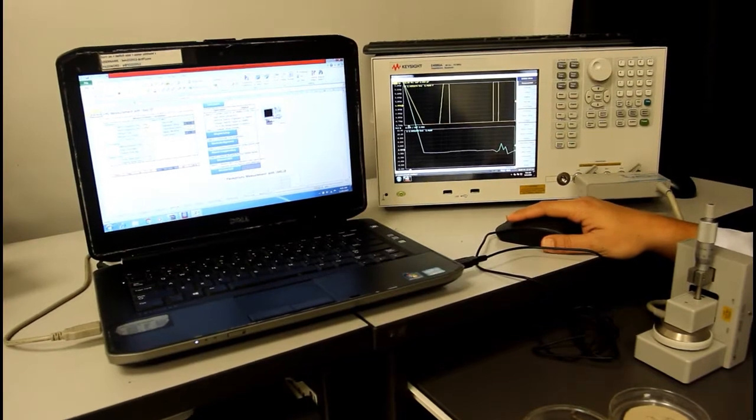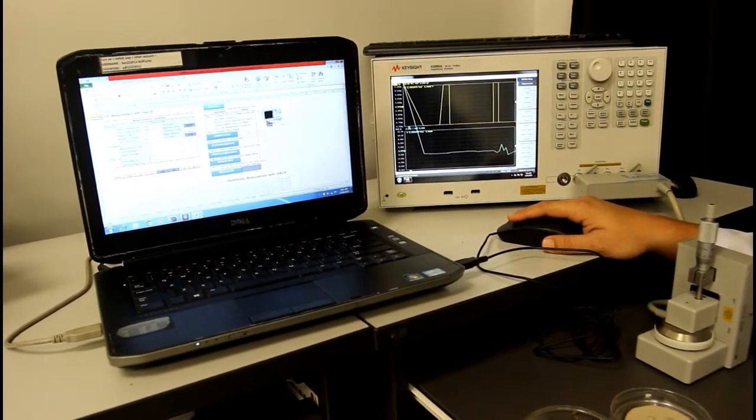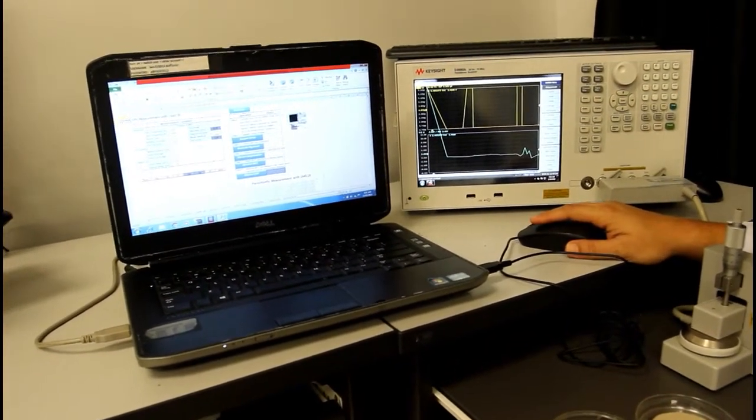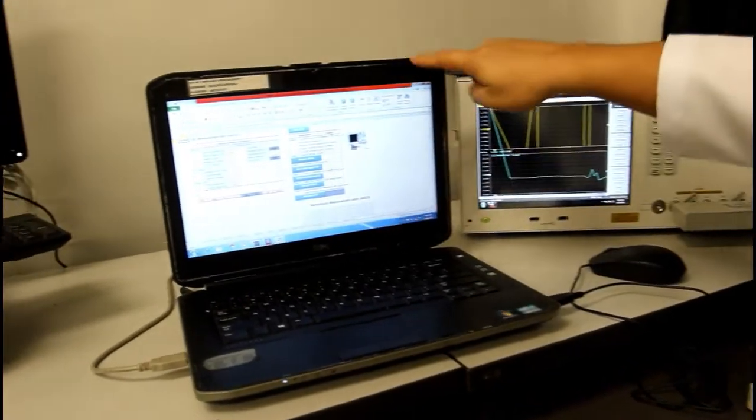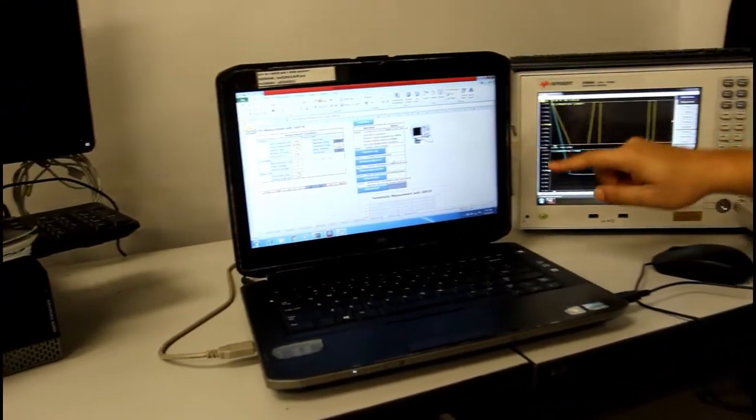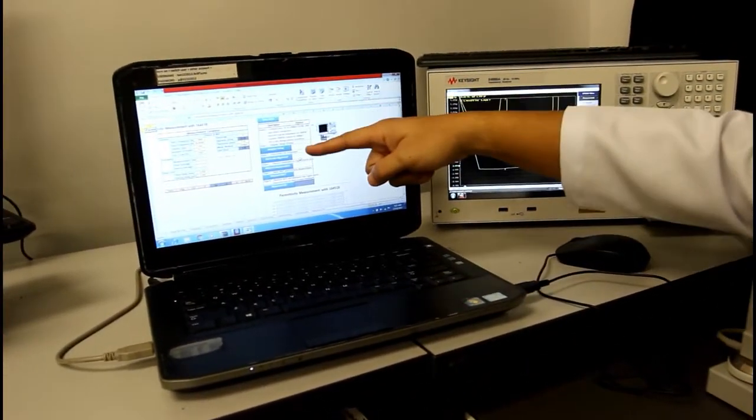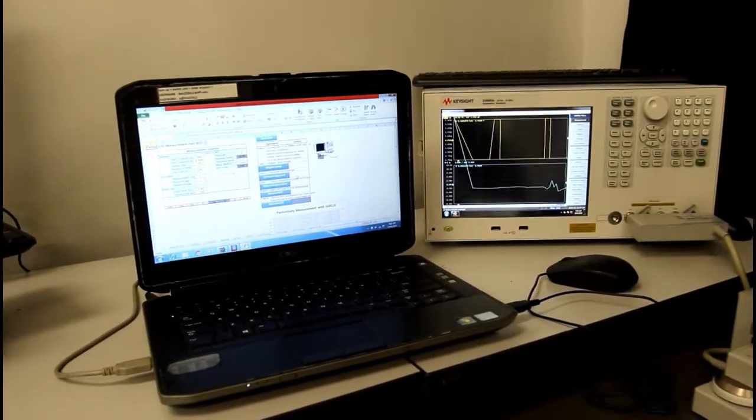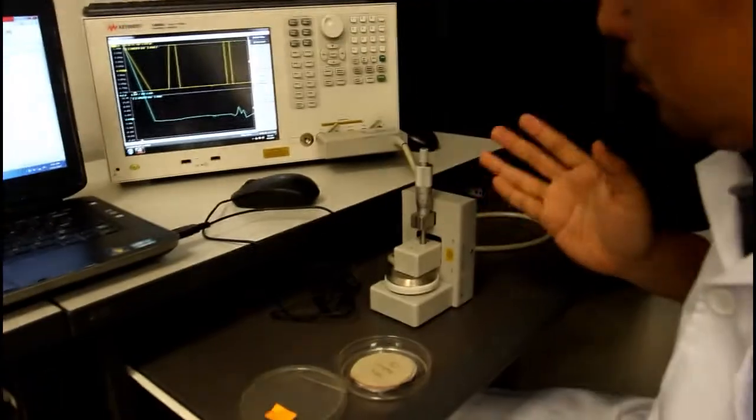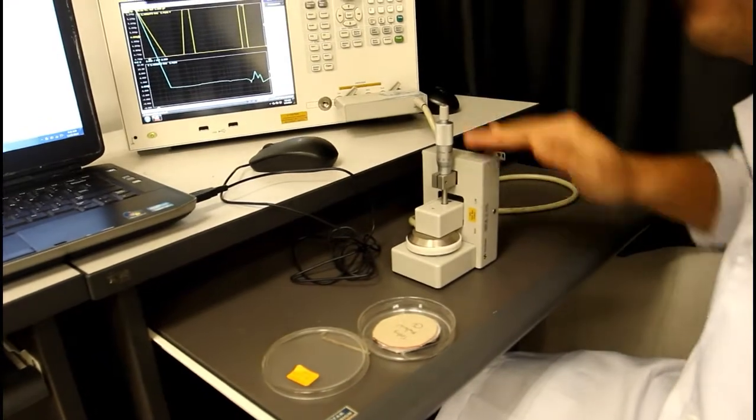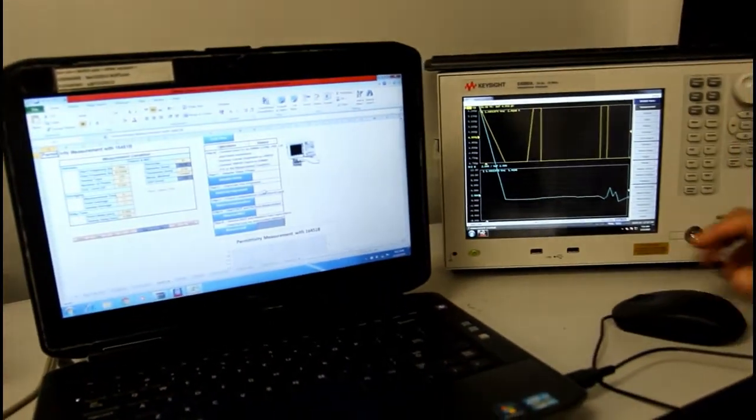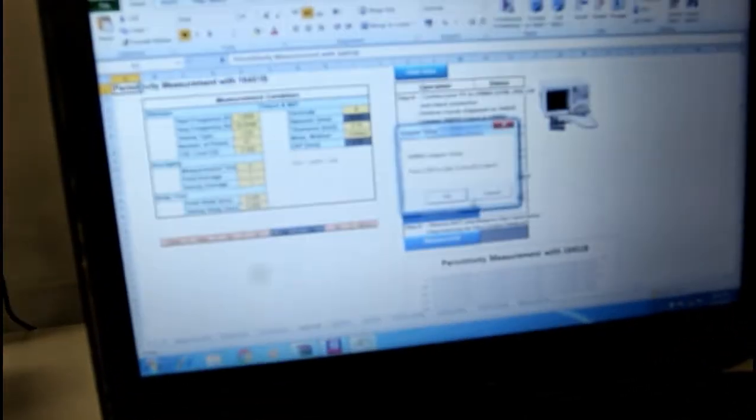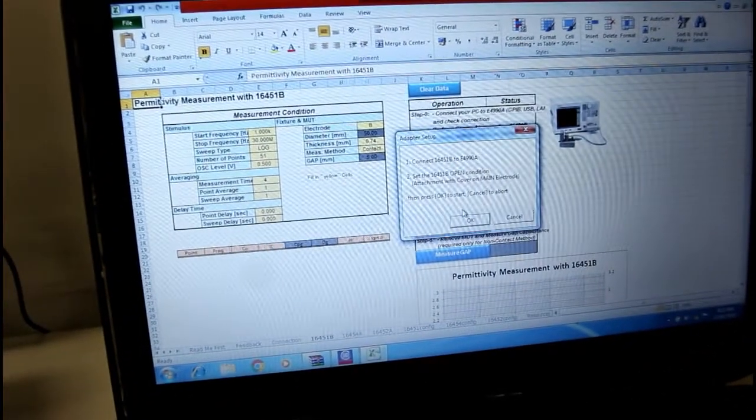Now, you have to understand that the procedure that I will show to you is not a procedure to set up the experiment, but more on the calibration of this instrument. Now, the first step is to set up the adapter. So, click on the adapter setup in your screen. Click on OK.